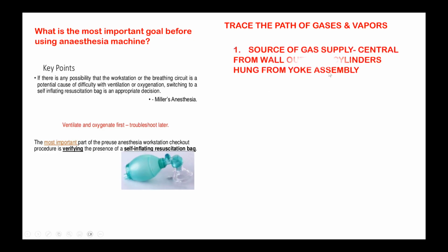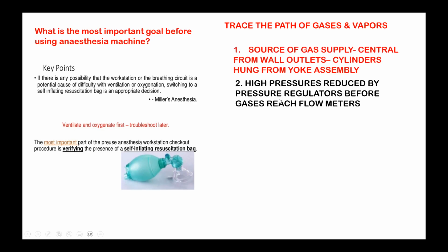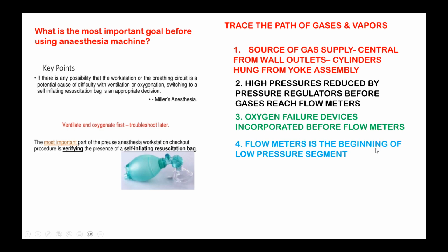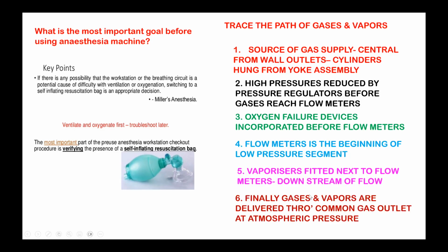If you trace that, sources may be the wall outlet or the cylinders hung from the hanger yoke assembly. The high pressure is reduced by a pressure regulator before the gas reaches the flow meter. Oxygen failure devices are incorporated before it goes to the flow meter. The flow meter is the beginning of the low pressure segment. Vaporizers fitted next to the flow meters are downstream. Finally, gases and vapors are delivered through the common gas outlet at atmospheric pressure.